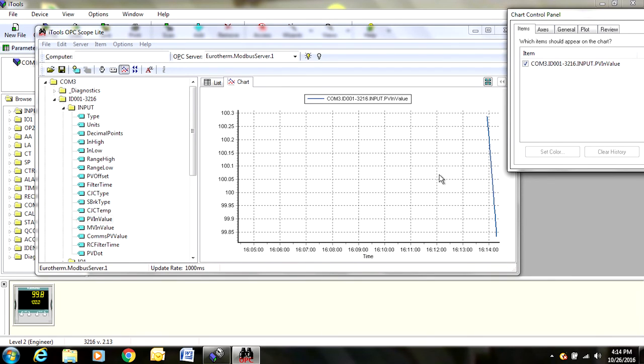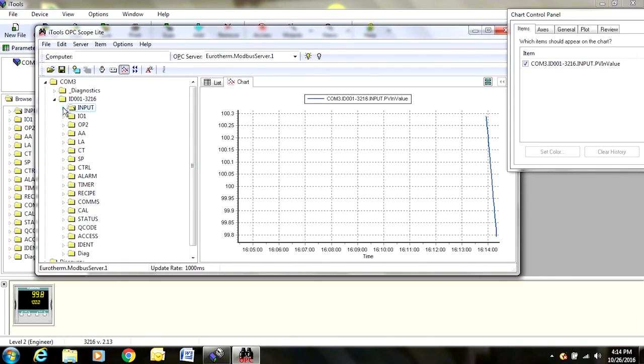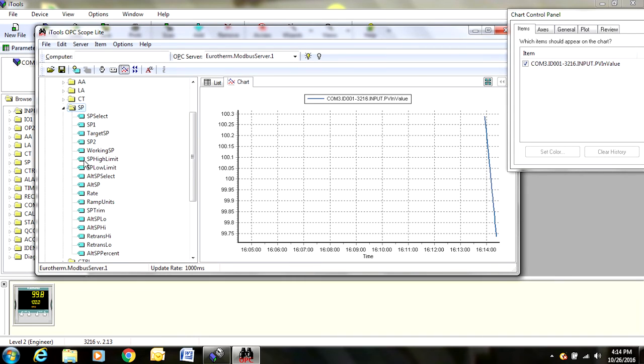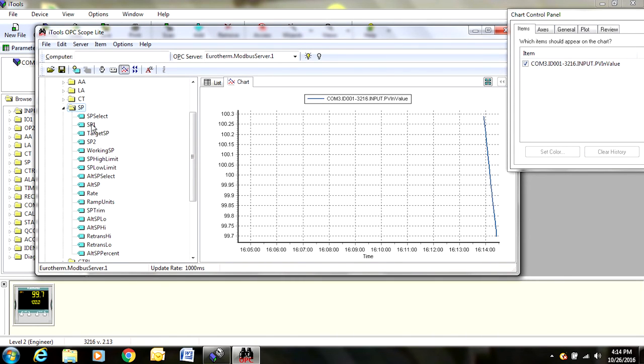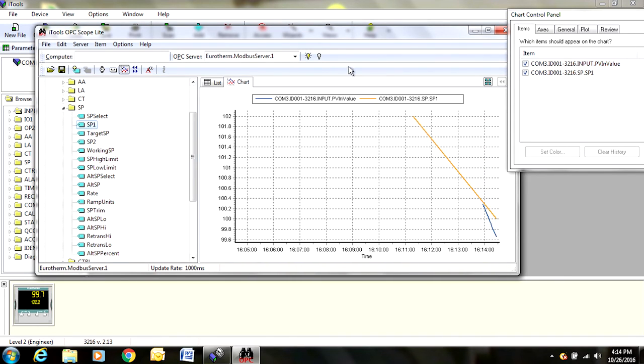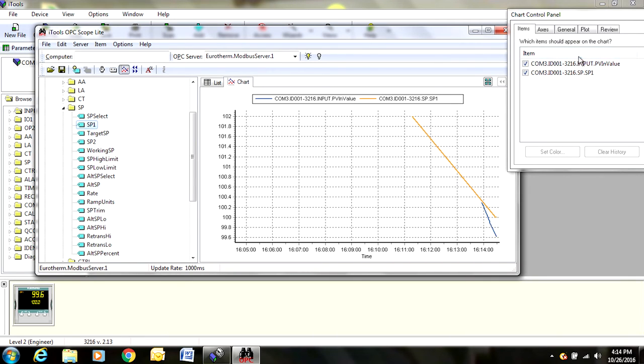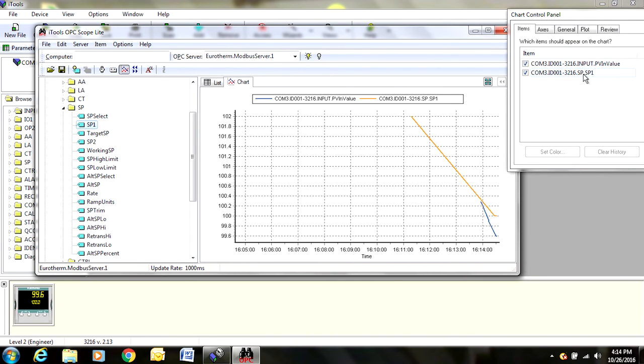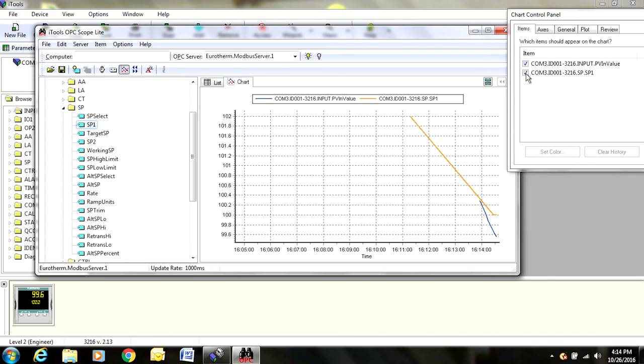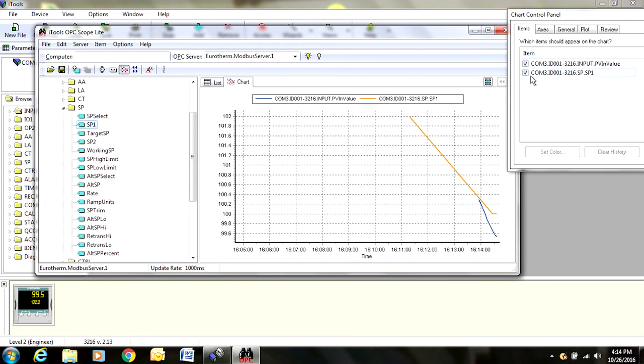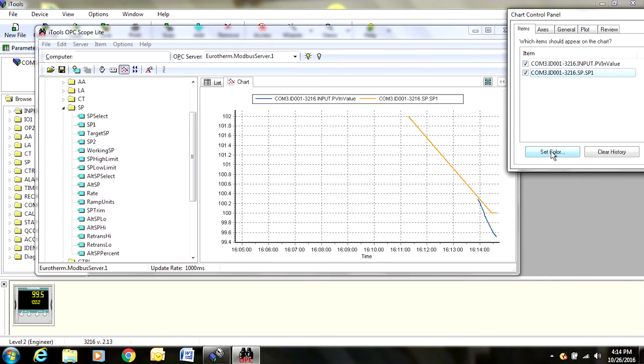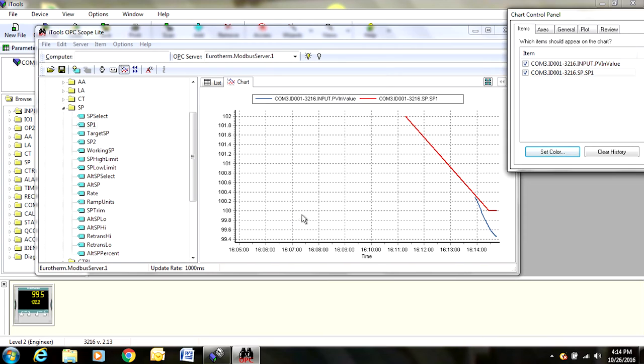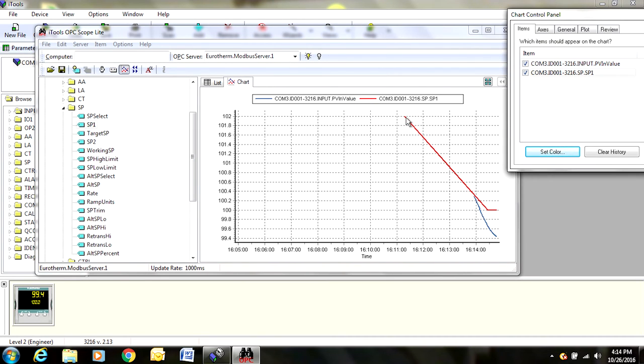We can also come over here to set point, SP, and then we can look at where the set points have been. If you notice over here, back in our control panel, it says SP1. It is already highlighted, which means it is going to show up here on the actual graph, but let's click here and I will show you how you can change the color. If you want to say, okay, let's make this red. Now our set point, when I first turned iTools on, it was at 102, we dropped it down to 100, and now it is held steady at 100.